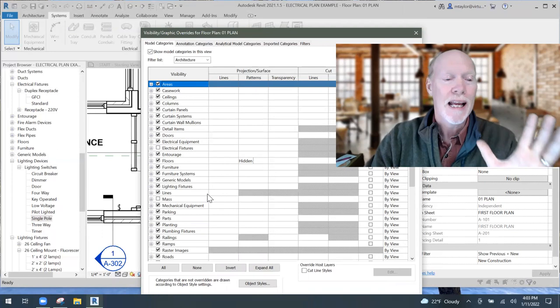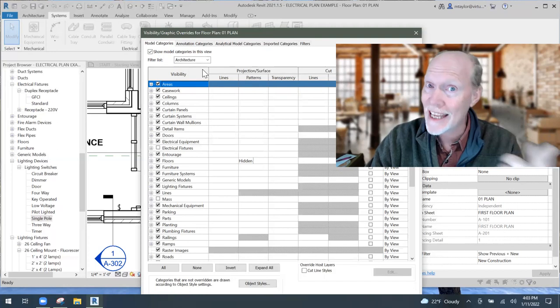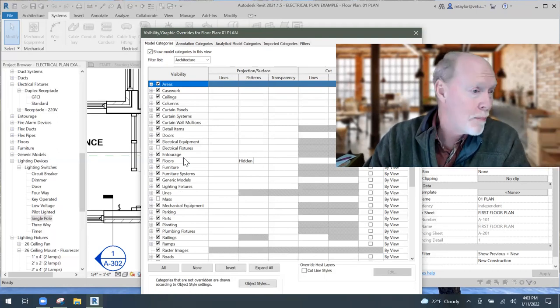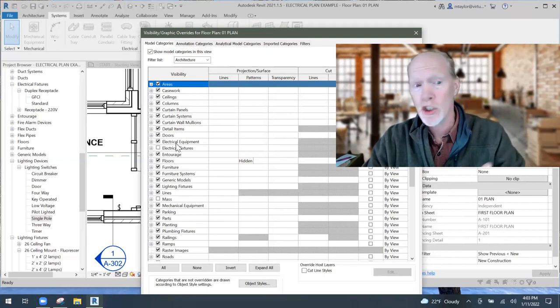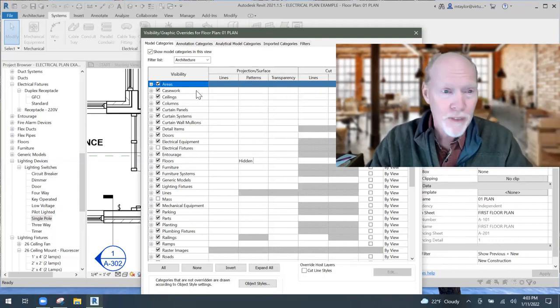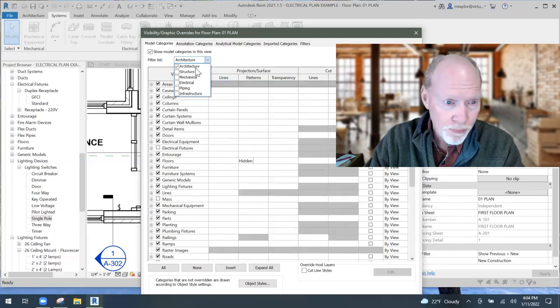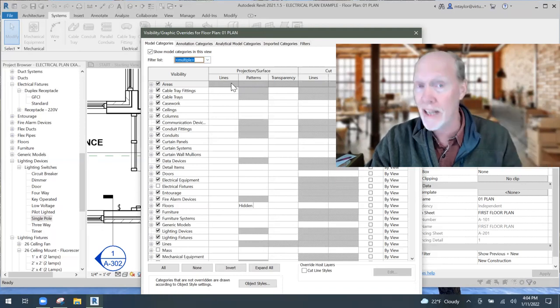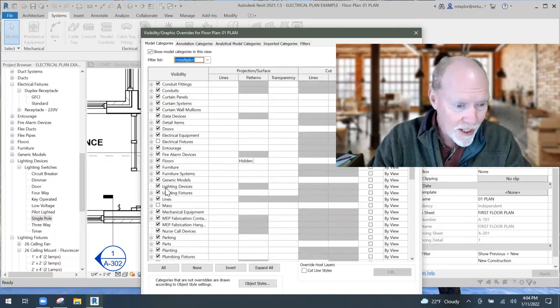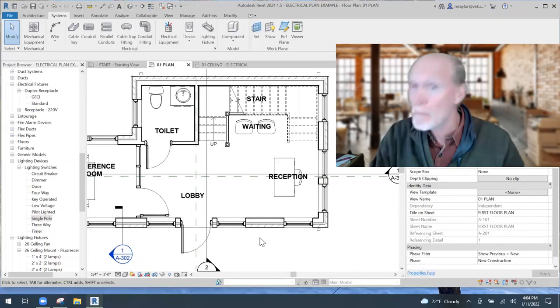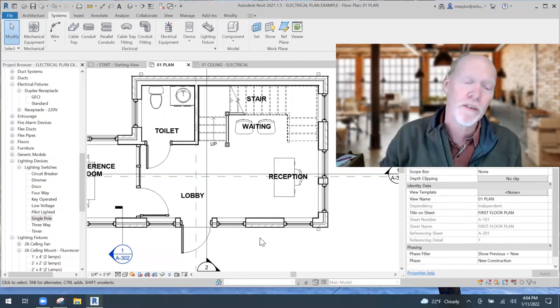Here's the key tip — I got a call on this just today. Someone asked how to turn those switches off, but their VG filter list at the top was set to Architecture, which only shows architecture items. Electrical Fixtures happened to be on that list because architects use some, but Lighting Devices — switches — were not. So on the filter list dropdown, check the box for Electrical. That makes all the electrical categories available. Scroll down and Lighting Devices is now an option. Uncheck it and hit OK, and your switches turn off in the floor plan.